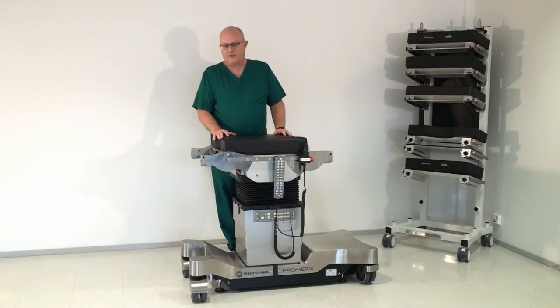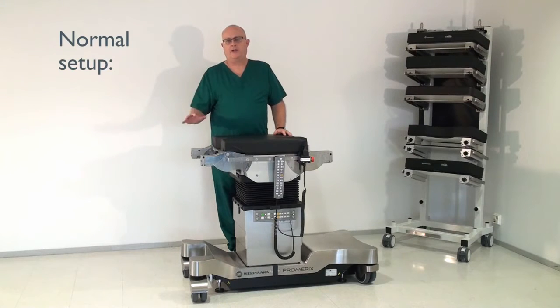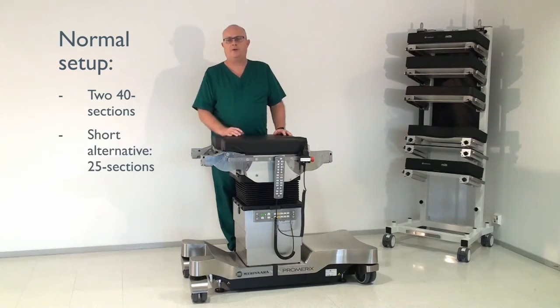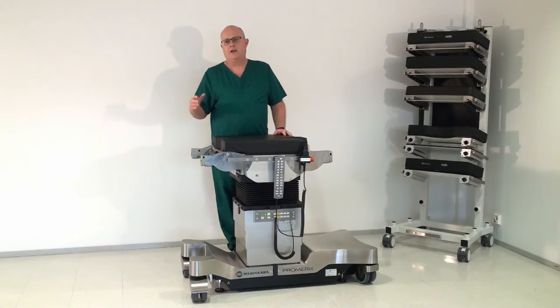There's several ways that you can set the table up. Normally it comes in a fairly normal setup with 40 mil sections on the main body of the table. We also produce 25 mil sections.